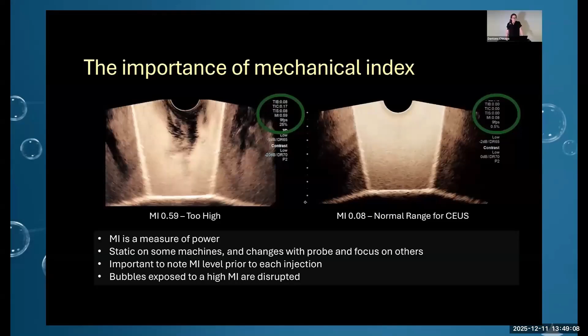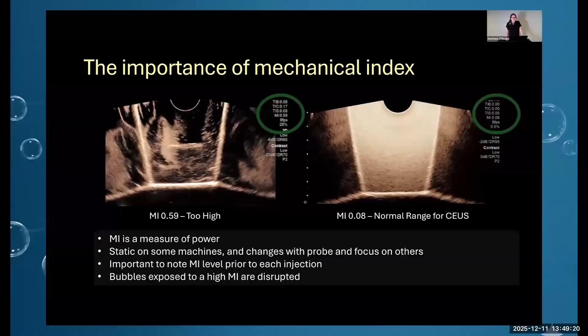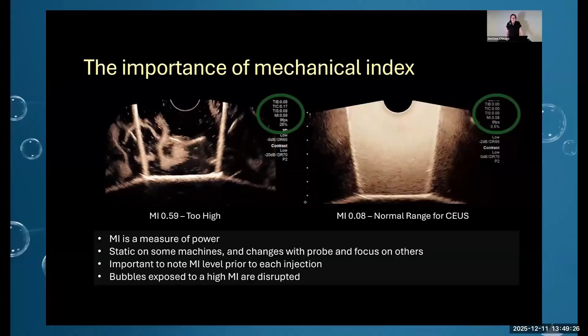So on the left-hand side, we have some bubbles that we've placed in a cup full of water, and we put the probe in the cup. And the mechanical index is about 0.59. And on the right-hand side, the probe placed in a cup of water with bubbles in it, mechanical index is about 0.08. So you can see the difference in what happens. You get avid bubble destruction on the left-hand side, and on the right-hand side, you have even distribution of bubbles from the near field to the far field in this cup.